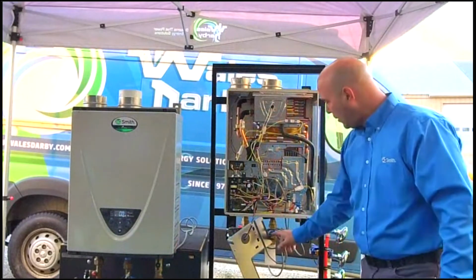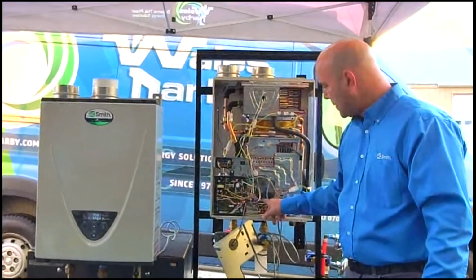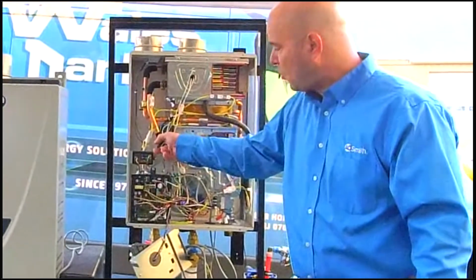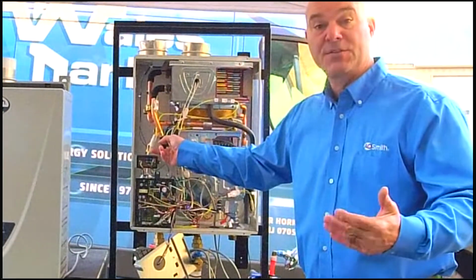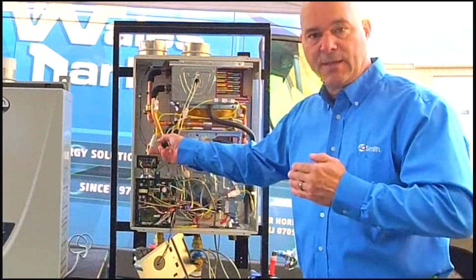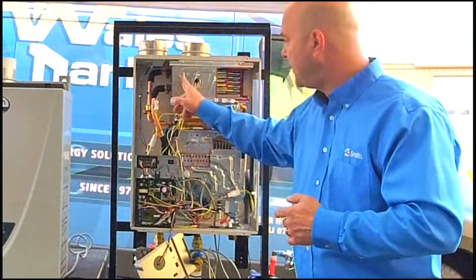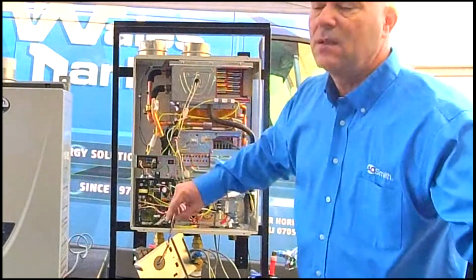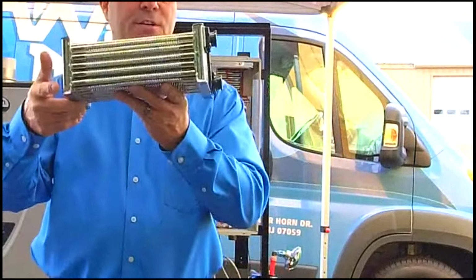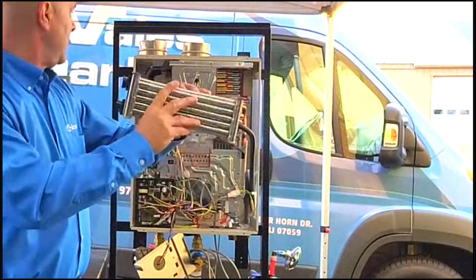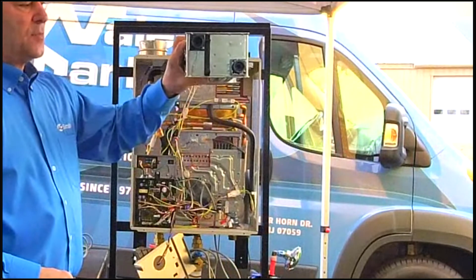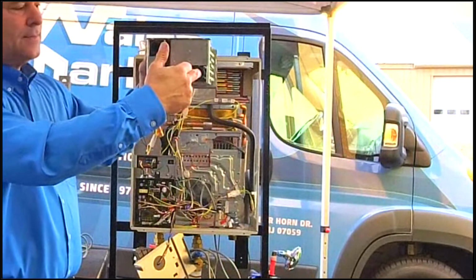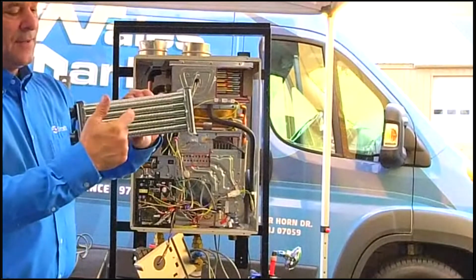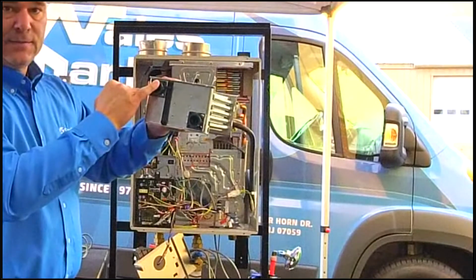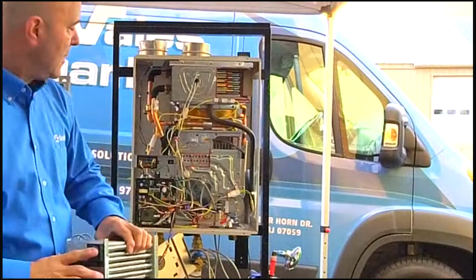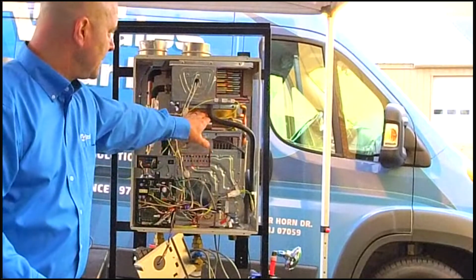So we enter through the cold, we go into the flow switch, we leave the flow switch and we come up to this port right here. It might be difficult for you to see, but there's a T block here. One side has a bypass. One side goes directly up into the secondary heat exchanger. So this is the secondary heat exchanger. This is a cutaway. It is in the unit just like that. There's your connection points. So the cold water goes directly into here. The water runs through the inside of these tubes and comes out here and goes down and around into the primary heat exchanger right here.